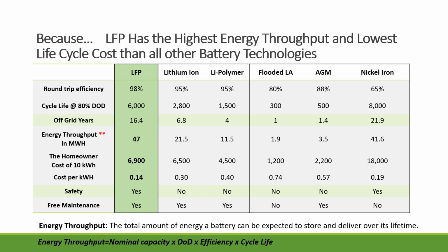Energy throughput is an important term. The energy throughput is the total amount of energy that a battery can be expected to store and deliver over its lifetime. This is the formula: energy throughput is equal to the nominal capacity of the battery, in this case 10 kilowatt hours, multiplied by depth of discharge, 80%, multiplied by efficiency, 98%, and multiplied by the guaranteed life cycles, 6,000. In that case, you will get 47 megawatt hours with one of our LFP10.